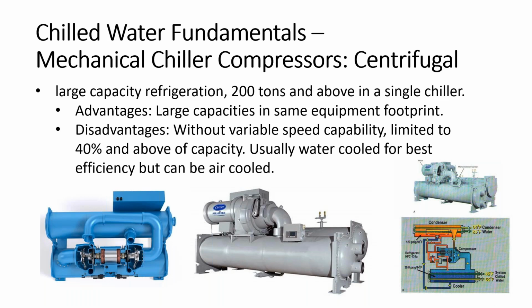If it's trying to push against a high temperature, it will push the refrigerant backwards. These are non-positive displacement. So if you have any trouble either on the suction, the inlet side, or the outlet side, refrigerant's going to get pushed backwards through the impellers and they will scream, they will make a noise. Whereas all of the compressors we saw before are all positive displacement. The refrigerant can only go one way, in to out. These, however, there's nothing dividing them except the speed of the machine. And if you run into problems, it will blow refrigerant backwards and it sounds terrible.